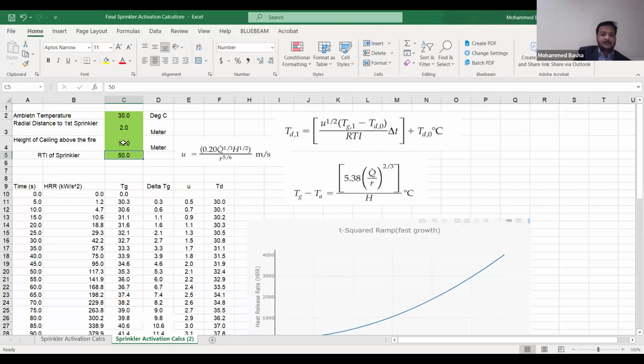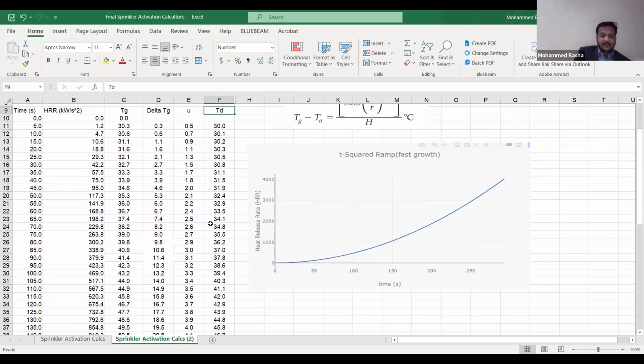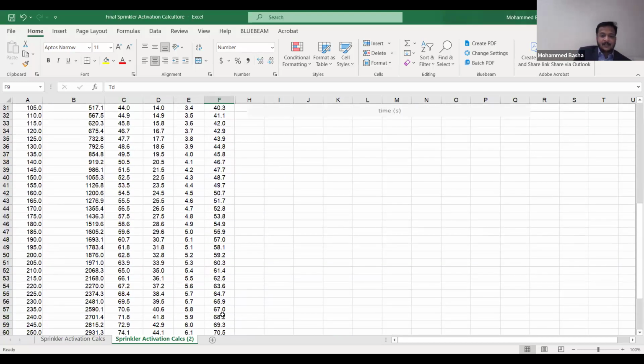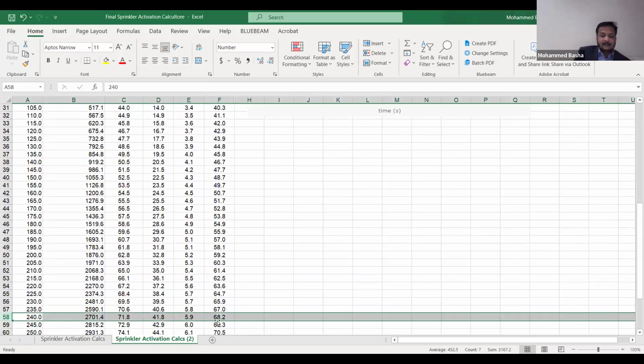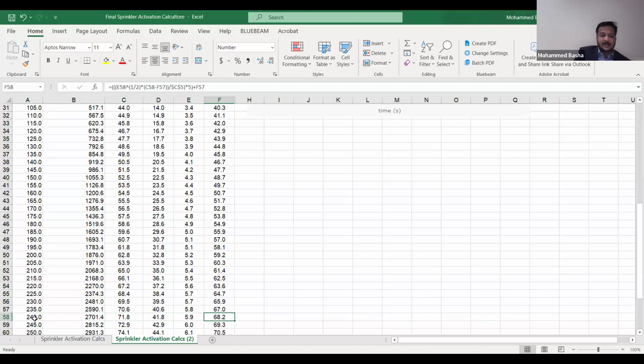When I put this value, you need to know what type of sprinkler you are going to use, in terms of temperature. The normal temperature used within a building is 68 degrees Celsius, right? So I need to see the TD, the detection temperature, where it reaches 68 degrees Celsius. The heat is developing, the ceiling jet velocity is here, whereas the temperature goes here. If I go down here, I reach the activation temperature of the sprinkler, 68.2 degrees Celsius, at 240 seconds after the fire starts to grow.